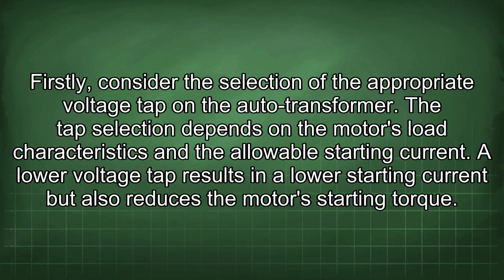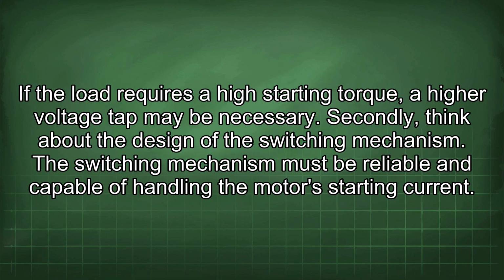Firstly, consider the selection of the appropriate voltage tap on the auto-transformer. The tap selection depends on the motor's load characteristics and the allowable starting current. A lower voltage tap results in a lower starting current but also reduces the motor's starting torque. If the load requires a high starting torque, a higher voltage tap may be necessary.